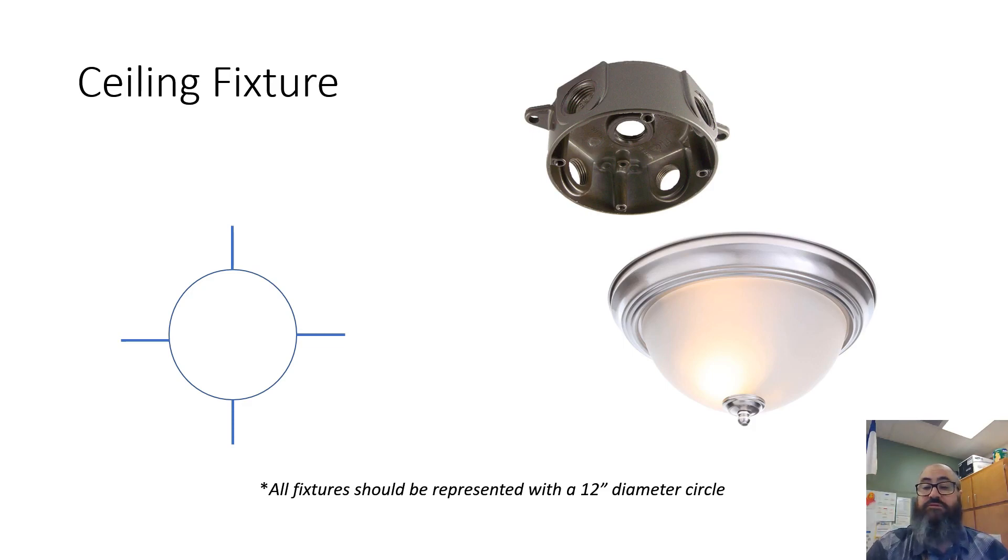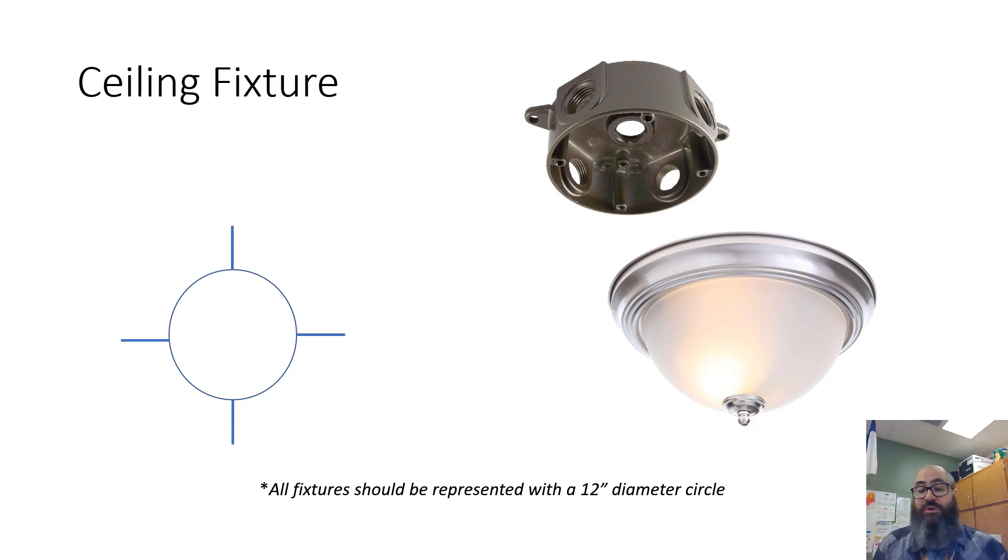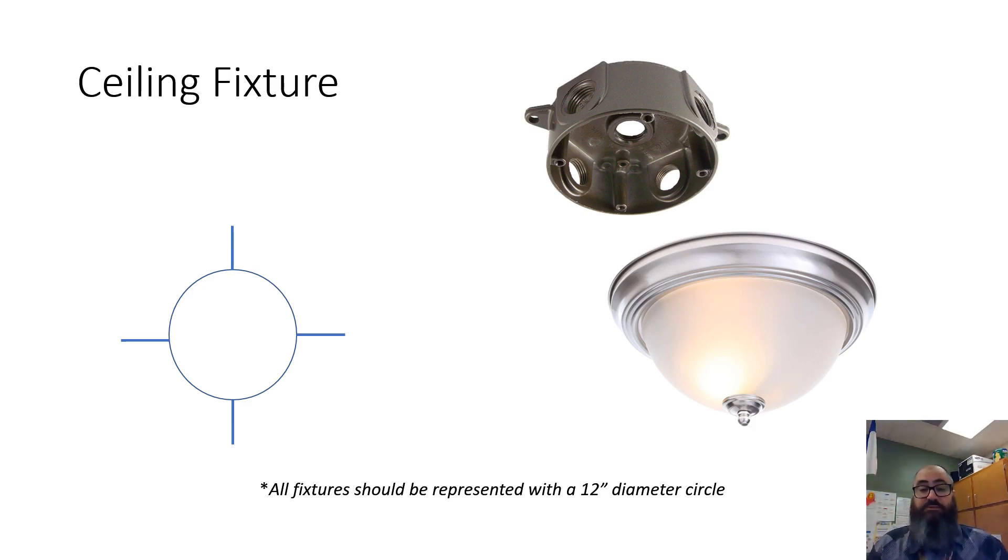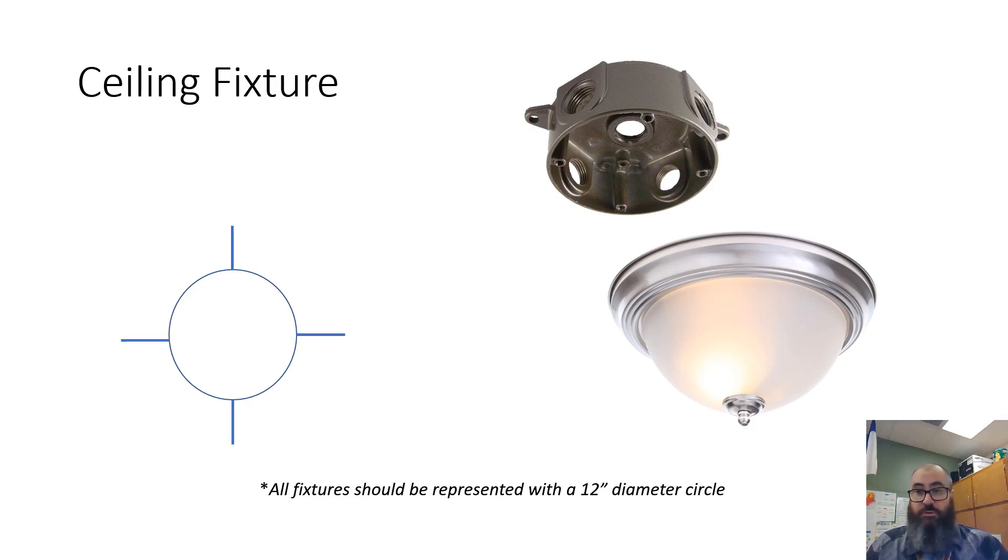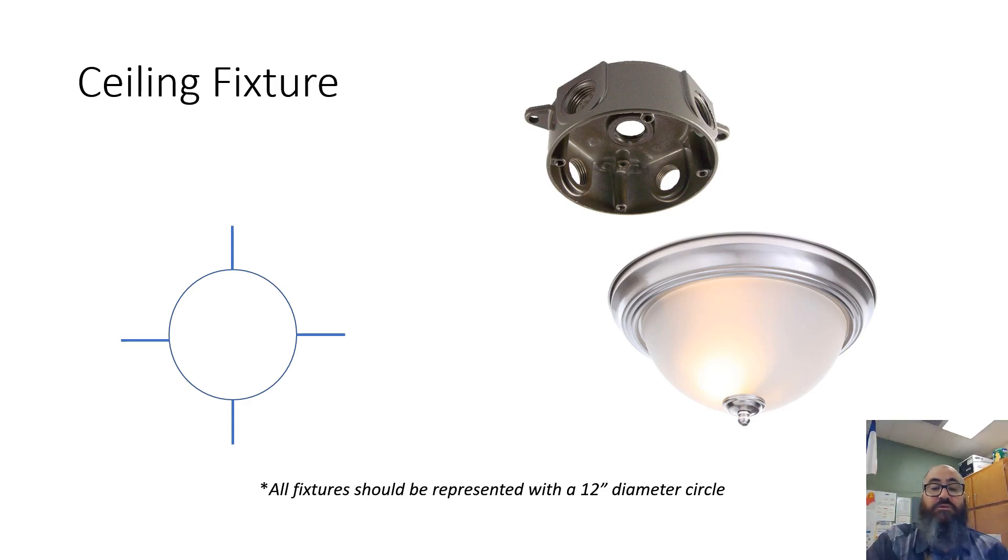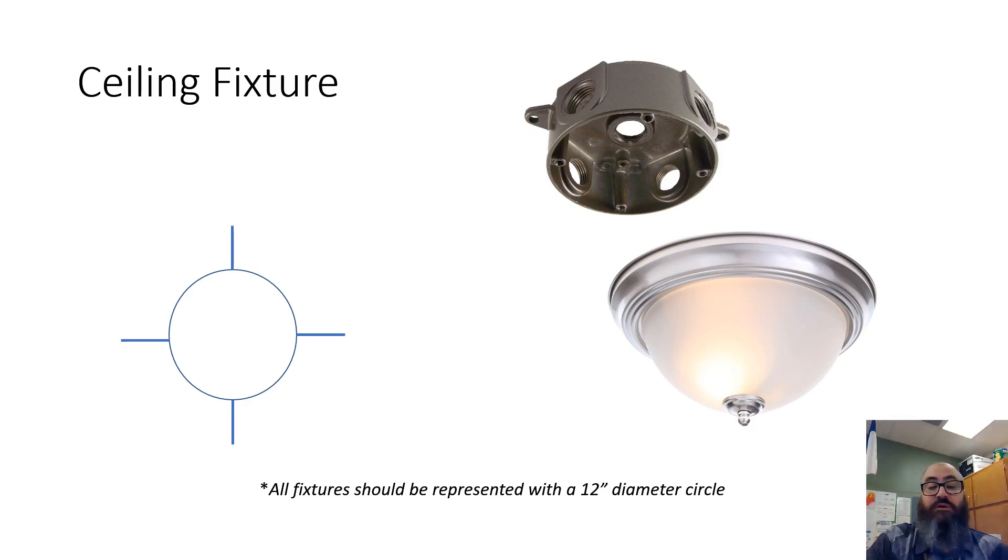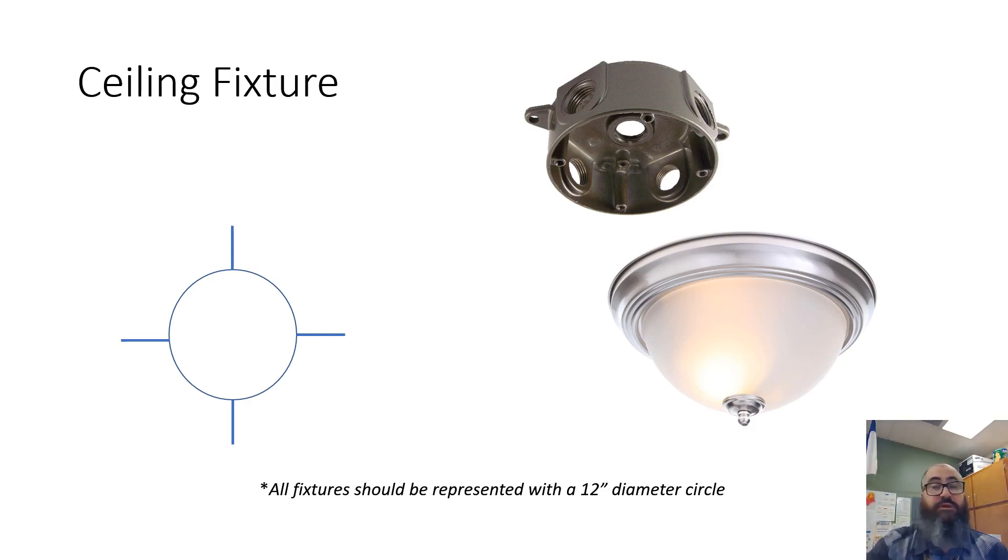This is the visible part down here. You'll never see the junction box unless you're installing or servicing them. One note at the bottom: all fixtures should be represented with a 12-inch diameter circle. There's no written rule that says you must use a 12-inch circle - it's mainly determined by whoever you're working for. For this class, use a 12-inch circle. The extension lines don't have any specific length, but be reasonable. You want to be consistent, so once you make one symbol, turn it into a block and use that same symbol across all rooms and plans.